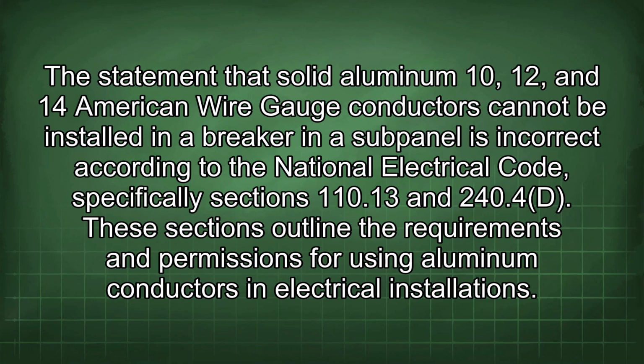The statement that solid aluminum 10, 12, and 14 American wire gauge conductors cannot be installed in a breaker in a subpanel is incorrect according to the National Electrical Code, specifically sections 110.13 and 240.4(D). These sections outline the requirements and permissions for using aluminum conductors in electrical installations.